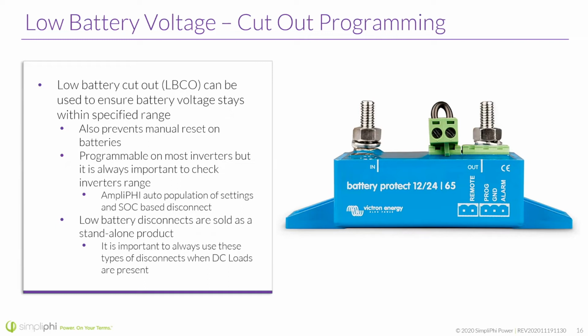Low battery cutout basically can be used to ensure battery voltage stays within the specified range. We'd rather that the system shuts down or goes into a standby mode, than the battery continue to discharge below its designated 0% state of charge. It also prevents manual reset on the batteries if it works correctly, meaning that the batteries can still charge and the system can still turn back on if the low battery cutout is programmed properly.